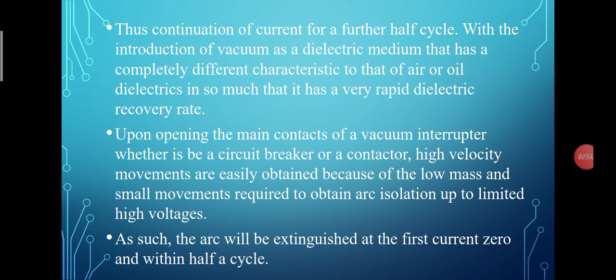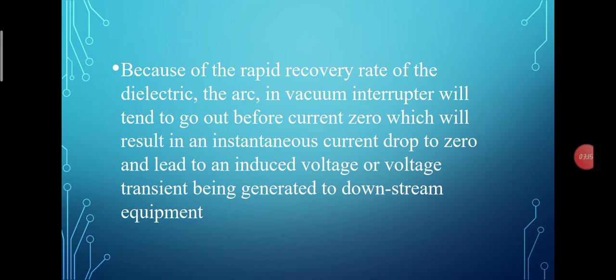Because of the rapid recovery rate of the dielectric, the arc in a vacuum interrupter will tend to go out before current zero, which will result in an instantaneous current drop to zero and lead to an induced voltage or voltage transient being generated to downstream equipment.